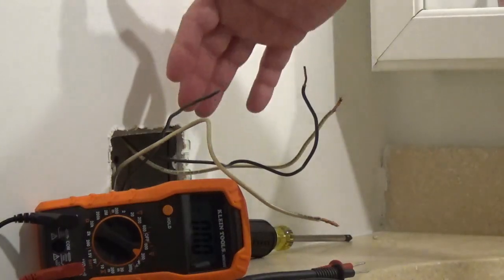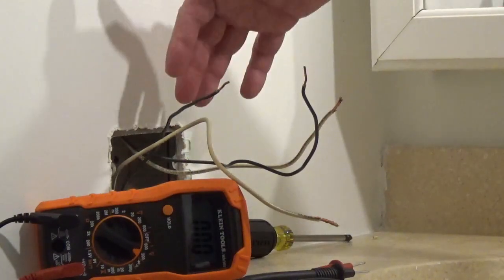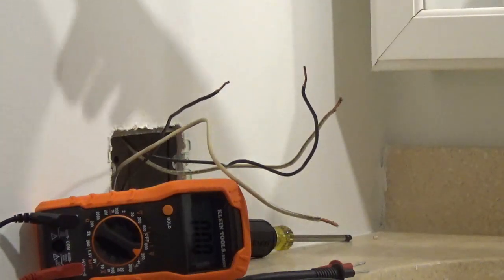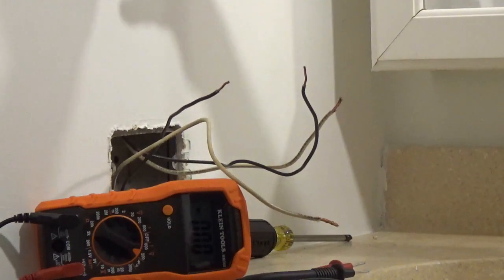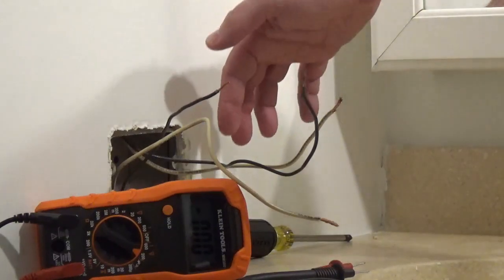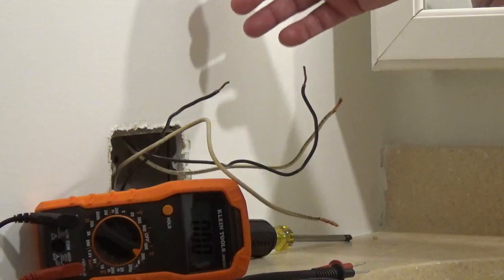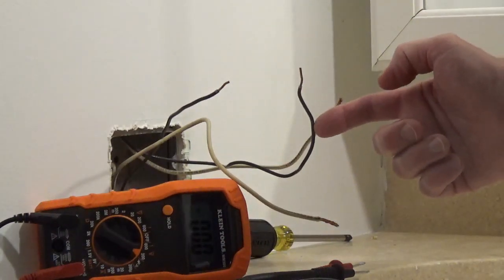If you have four wires plus a ground or four wires with no ground wire, you're going to be using the line and the load side. For this, we're going to have to test to find which pair of wires are coming from the service panel. So we're going to be testing to find a hot wire.